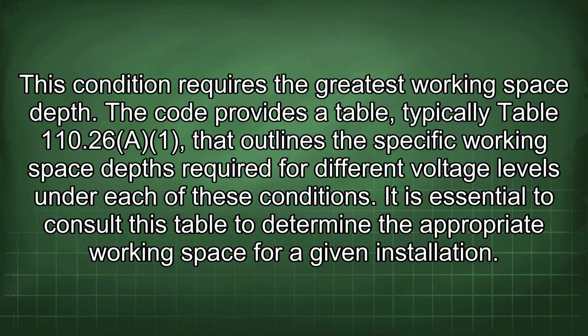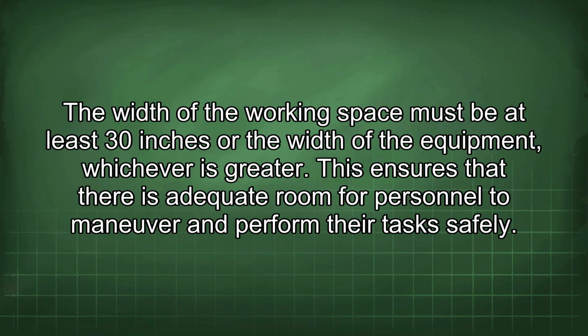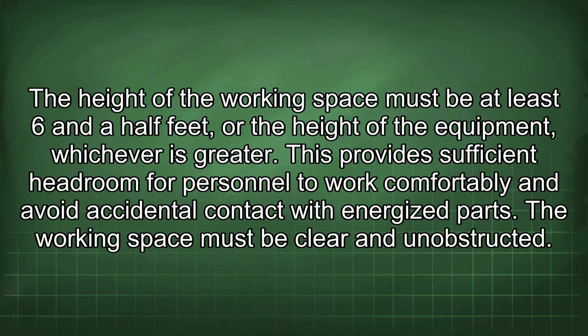The code provides a table, typically Table 110.26(A)(1), that outlines the specific working space depths required for different voltage levels under each of these conditions. It is essential to consult this table to determine the appropriate working space for a given installation. The width of the working space must be at least 30 inches or the width of the equipment, whichever is greater. This ensures that there is adequate room for personnel to maneuver and perform their tasks safely. The height of the working space must be at least 6.5 feet, or the height of the equipment, whichever is greater. This provides sufficient headroom for personnel to work comfortably and avoid accidental contact with energized parts.